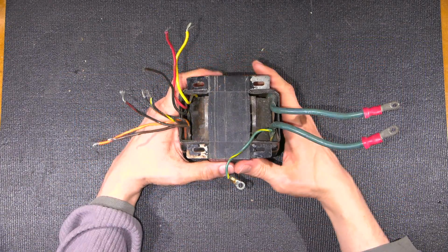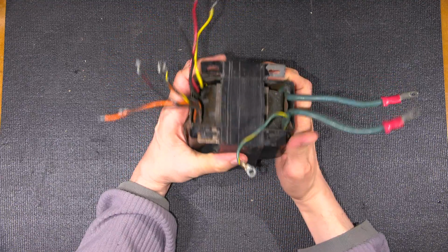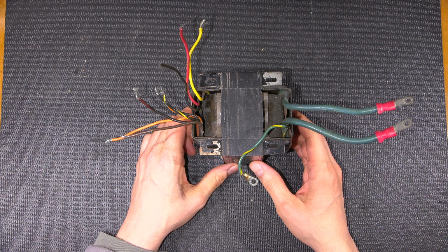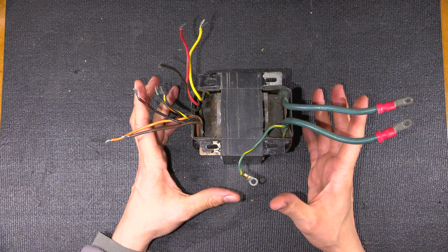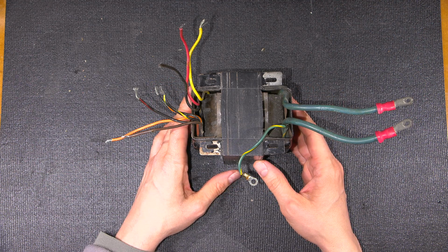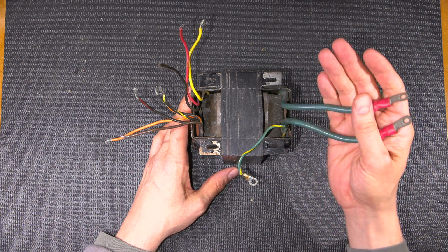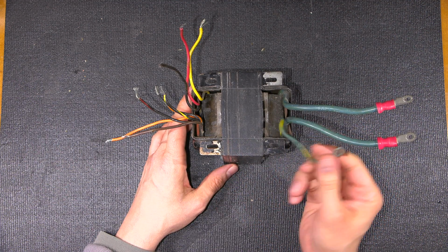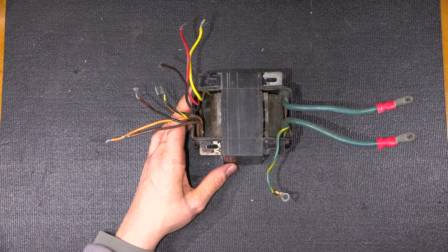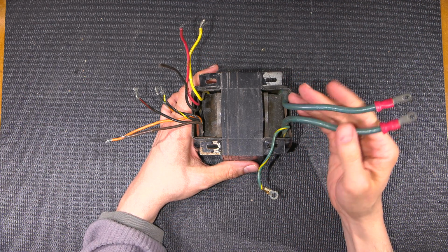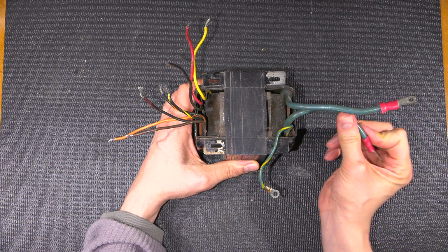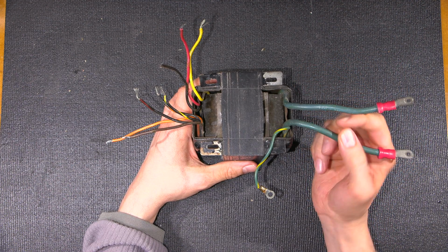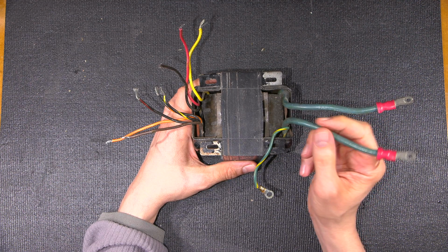I had to zoom out for this transformer here a little bit. So, from what we've already looked at, what can we tell from this transformer here? So you might want to take some guesses. If you do, pause the video and I'll explain this now. So we have 2 really large green leads on this side, and we have a green lead with a yellow stripe. So what does that tell us? Well, first of all, we know that these are the secondary side here, and these 2 large green leads are going to be the filament supply for some very large vacuum tube or vacuum tubes.